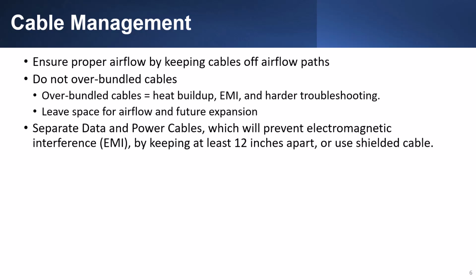Ensure proper airflow by keeping cables off airflow paths. Do not overbundle cables. Overbundle cables equals heat buildup, EMI, and harder troubleshooting. Leave space for airflow and future expansion. Separate data and power cables, which will prevent electromagnetic interference or EMI by keeping it at least 12 inches apart, or use shielded cables.